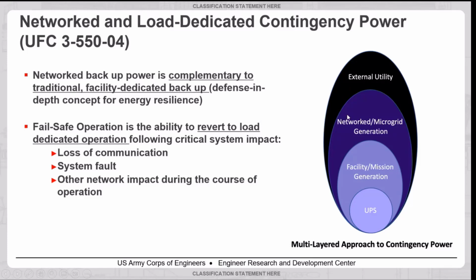So the idea here is that when something bad happens, whether it's loss of communication within the microgrid, some sort of fault in the microgrid's distribution system, or anything else, we can fall back down those layers so that the critical loads still receive power.